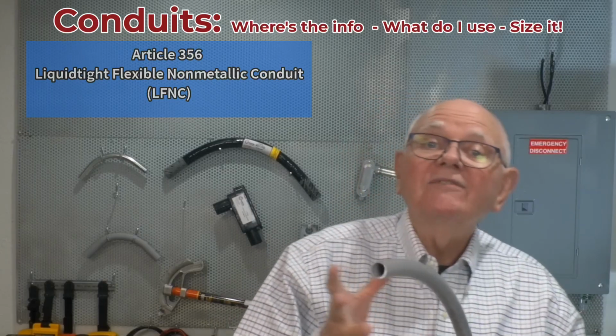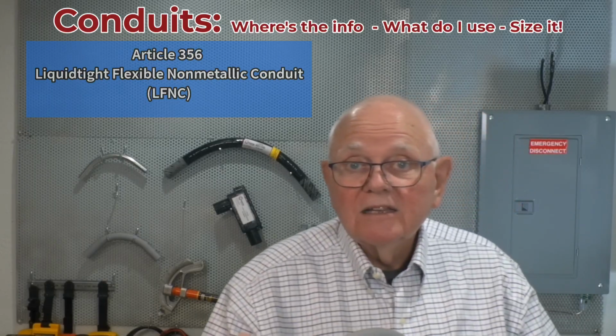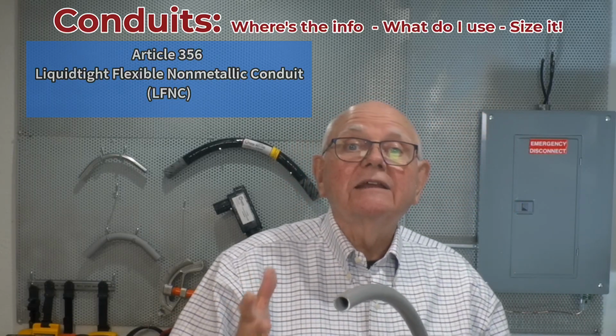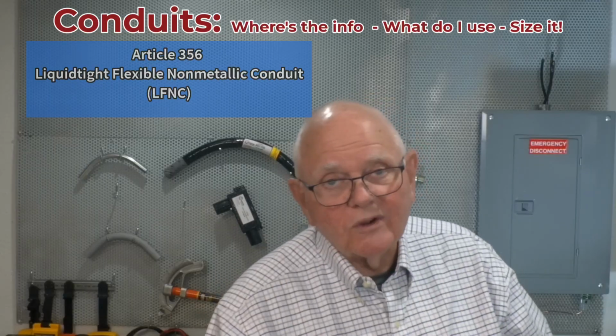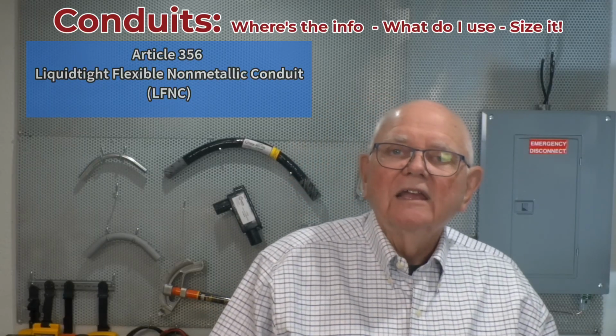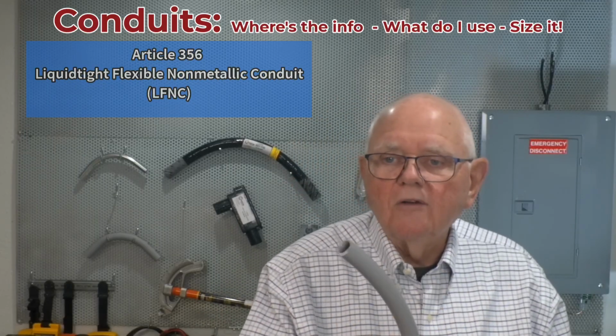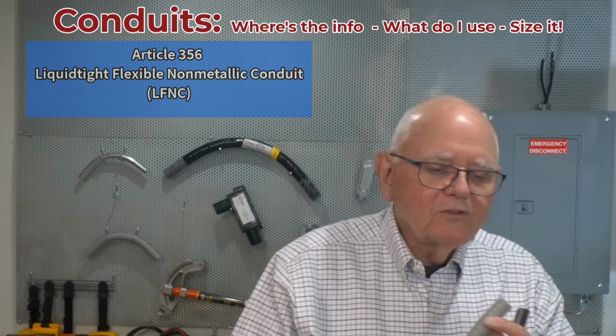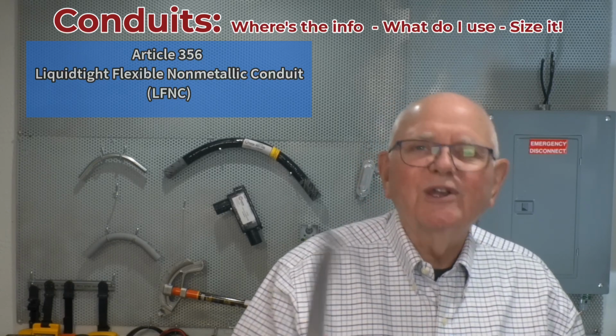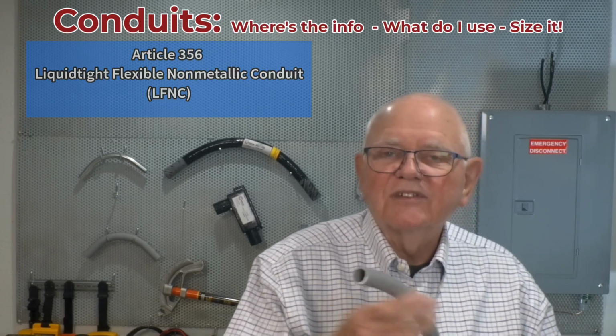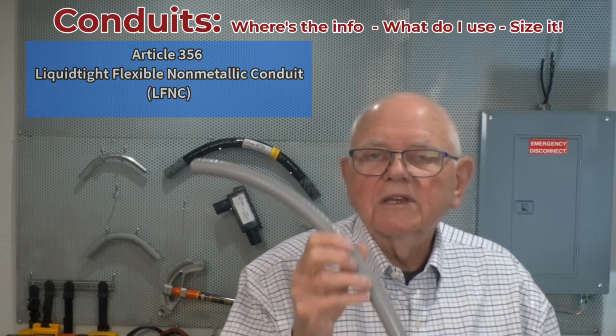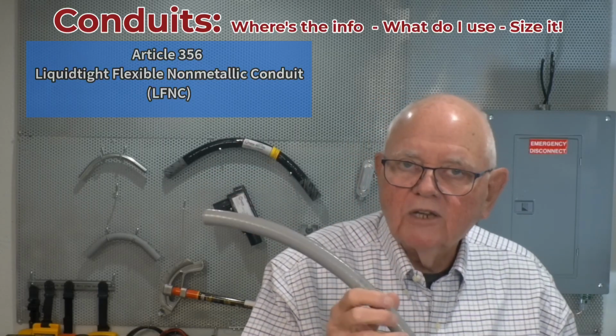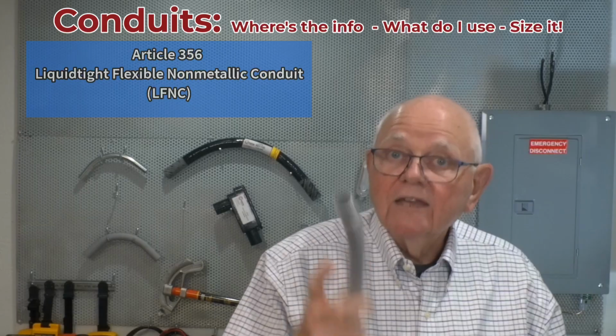And then LFNC-C, which can also just be abbreviated LFNC, according to the informational note there, has no reinforcement at all. Well, I normally wouldn't look at it and tell you what type of reinforcement it has. I can't tell. But you just look on the labeling. Of course, it's required to be marked, and it'll let you know what it is.